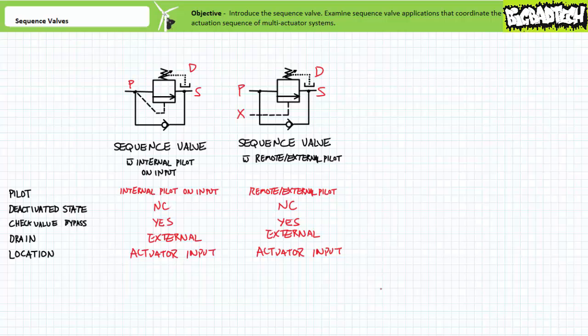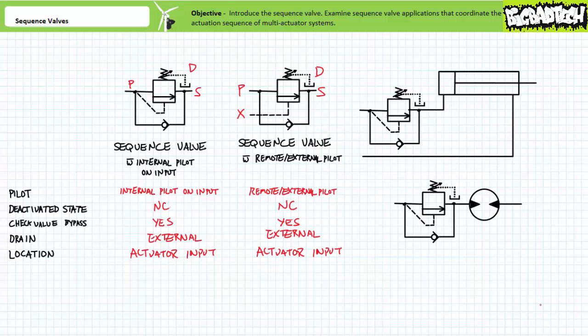External drains are customarily routed back to the reservoir above normal fluid level to ensure free movement of the drain fluid and no back pressure develops in the drain line. Finally, sequence valves are customarily found on the inputs of actuators and coordinate or sequence the action of multi-actuator systems. Note the term input is relative in nature, since both ports of a double acting cylinder or bi-directional hydraulic motor could rightly be considered either an input or output depending upon direction of flow.